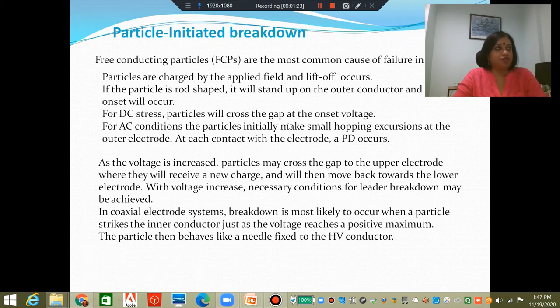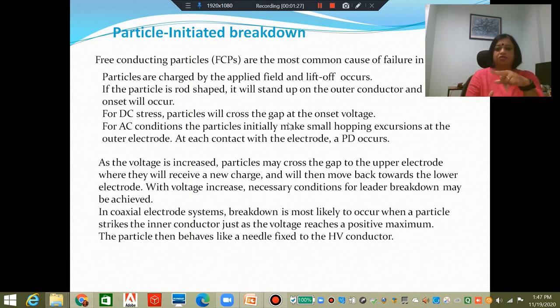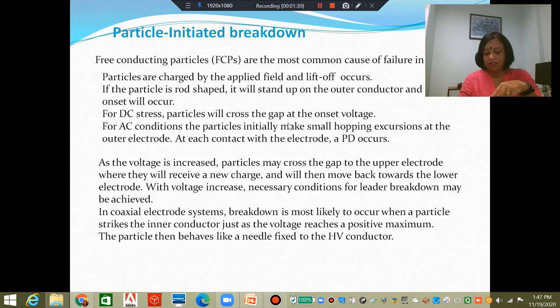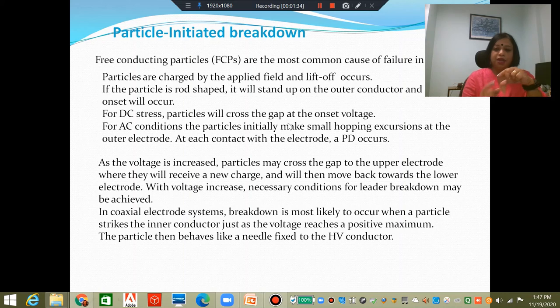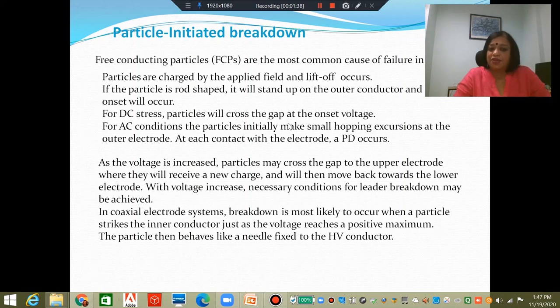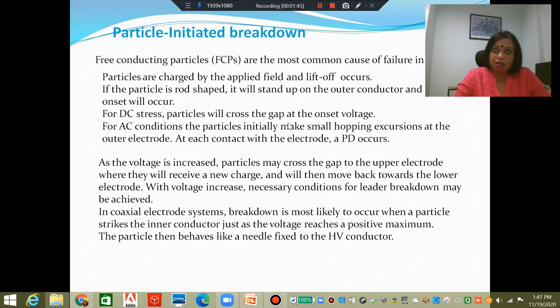If these particles are rod-shaped rather than spherical, they will stand up on the outer conductor because they will have non-uniform charge and behave like a dipole. There will be considerable field intensification, and that can result in partial discharges initiating from these particles.